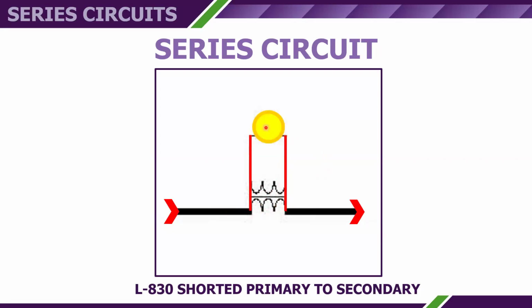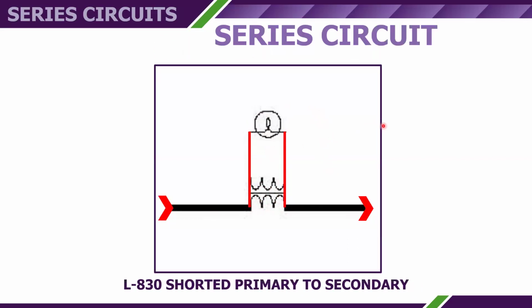And since it's 6.6 amps, that lamp is still happy. It's getting the current that it requires to operate. It's going to run along quite well until at some point in time the lamp itself fails. And you go out there with your fingertips and start replacing lamps, and you could put your fingers on 5,000 volts right here. There's no indication of that being a shorted transformer. Lamp burns out, you put your fingertips on it, and you become part of the circuit.